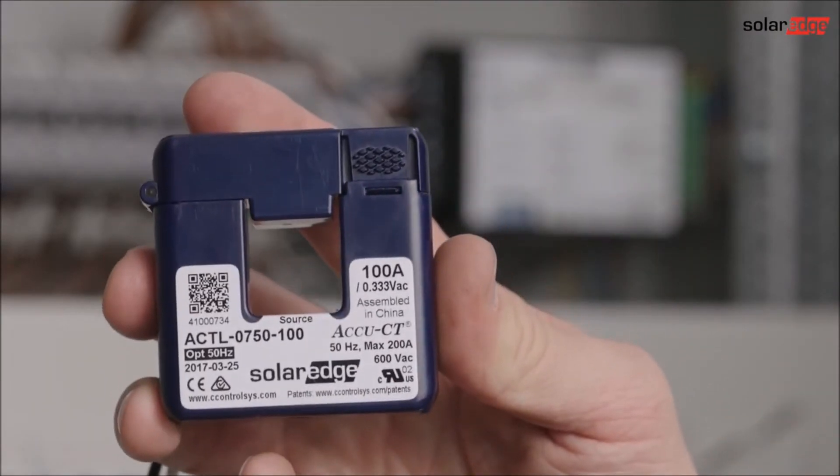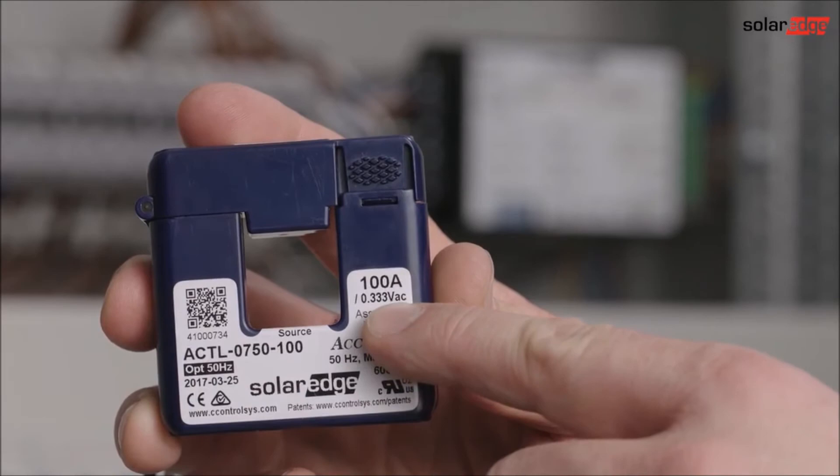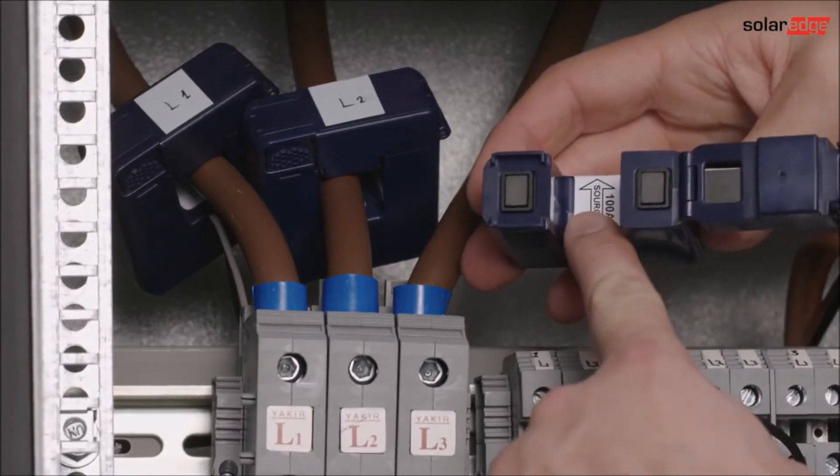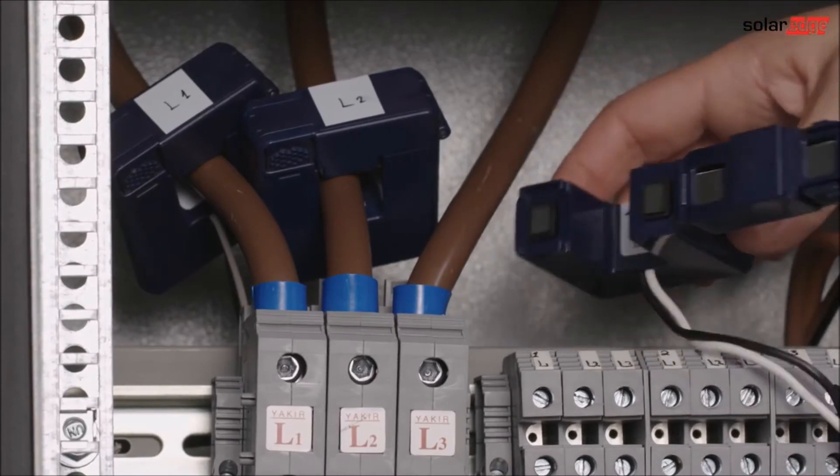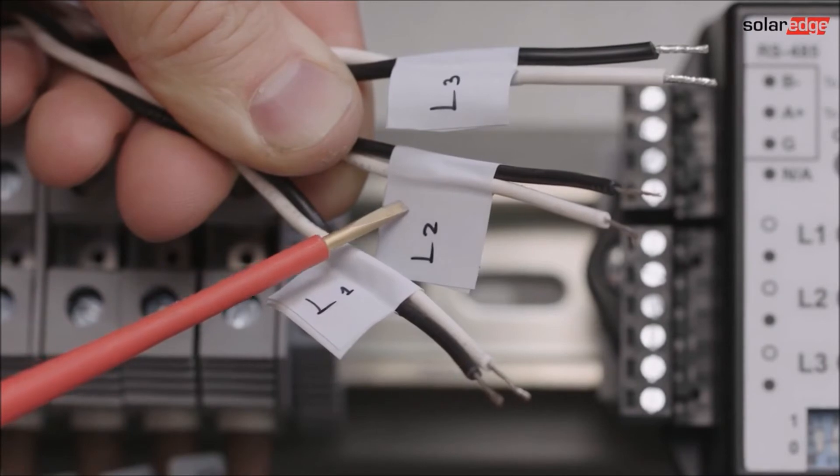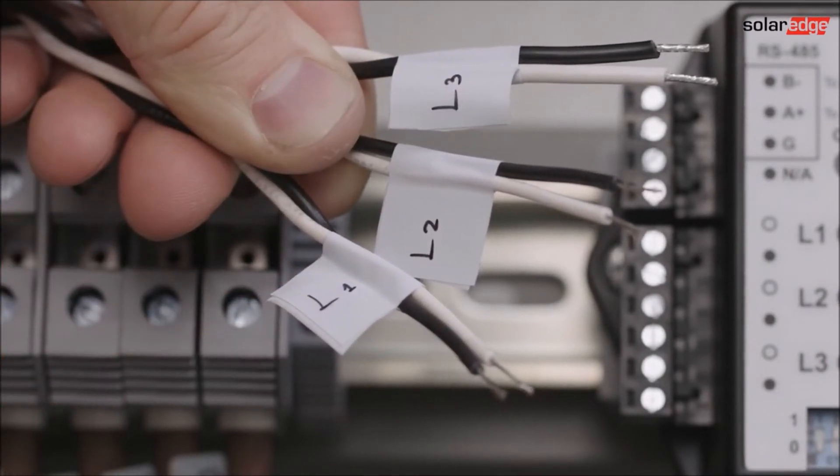Let's continue with the CTs. Each CT clamps around one of the main power supplies phase wires. They should be installed at the grid connection point and the arrow on the CT should point toward the grid connection. Make sure to keep the CTs in the same order as the AC wires. L1CT to L1 phase and so on.